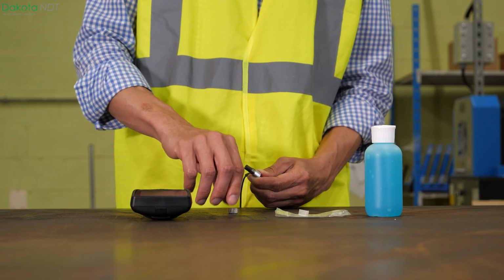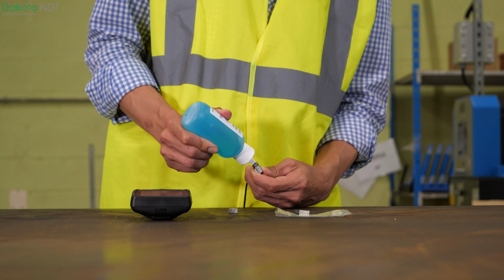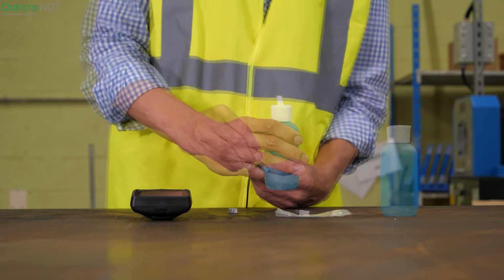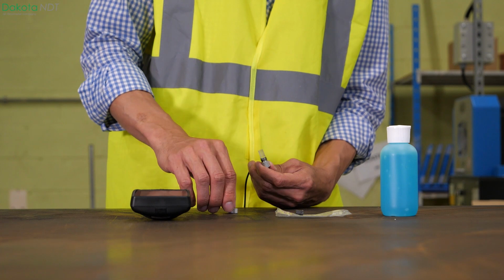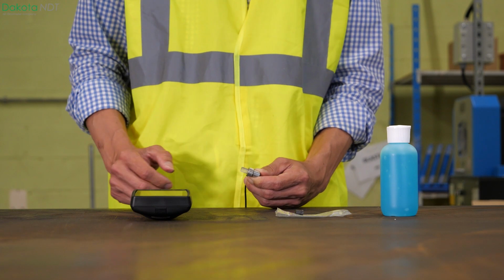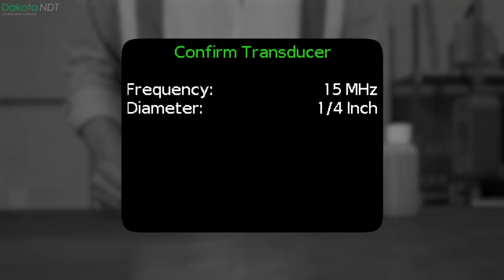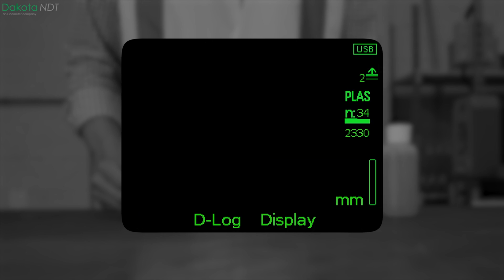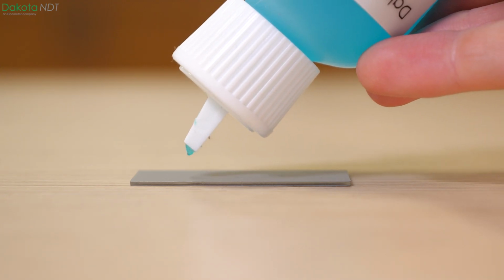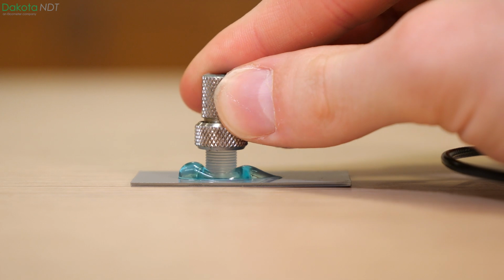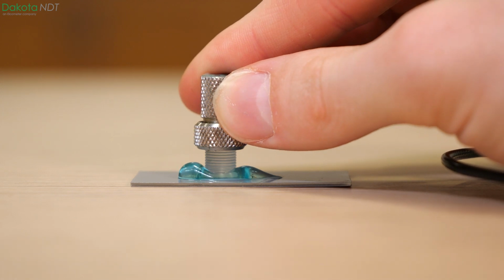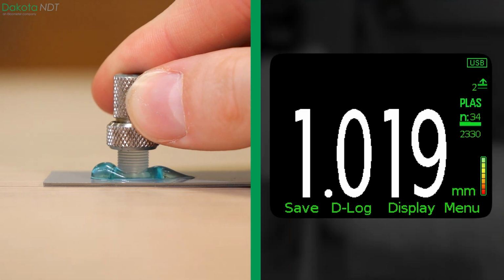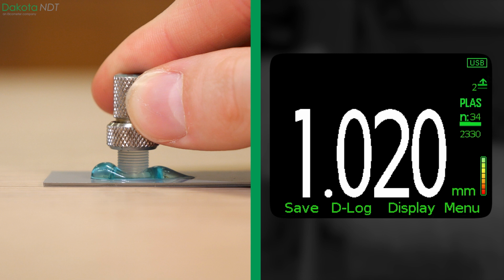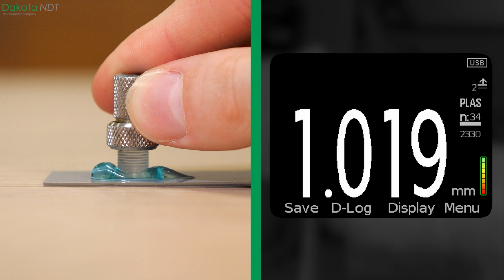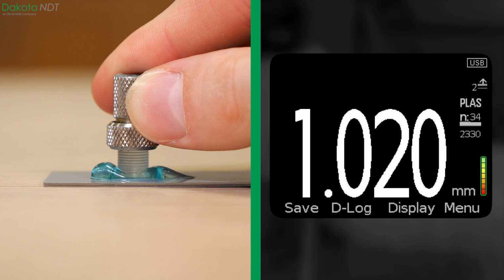Whenever you change delay lines, you should ensure there is a small amount of ultrasonic couplant between the delay line and the transducer, making sure there is no air between them. And always remember to change the delay line setting within the gauge. When measuring on materials that deflect or absorb the ultrasonic signal, the DakotaNDT PCX gauges only allow you to save a measurement if the signal strength indicator is in the green, avoiding false or incorrect readings.